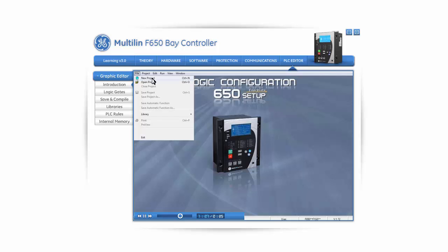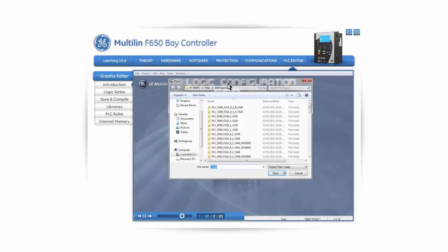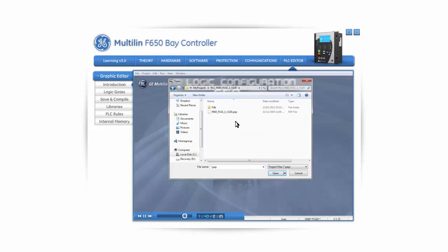Now let's take a look at the built-in logic of the F650. To open a pre-built logic file, go to the 650 PLC Editor and click on Open. When the EnerVista 650 software is installed, it will automatically have access to all the built-in logic that the F650 relay has. Choose the folder that corresponds to the model of the relay being used. For example, if the relay's model number is F650MZDF1G0HIR, then select PLC_F650_F1G1_1_V220, since it is the closest match. After choosing the correct folder, open the PEP file — the project file — and the built-in logic of the F650 will be displayed.